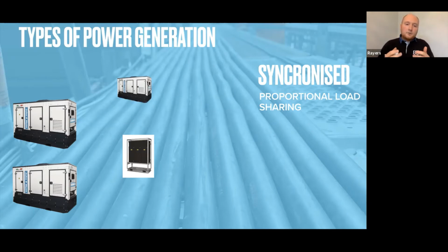You can program the panels so all of them work as hard as they can when they need to, but at times when the load is very low, typically overnight, the larger machines would shut down and the smaller machine would just maintain the load overnight. The good thing with that system is if that small machine then had a fault, one of those larger machines would be called upon to start and deliver the power to keep it going.